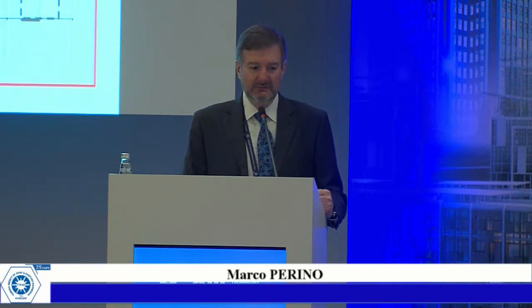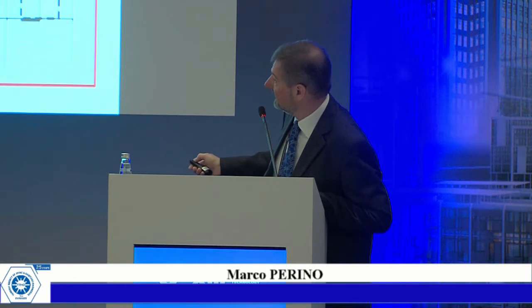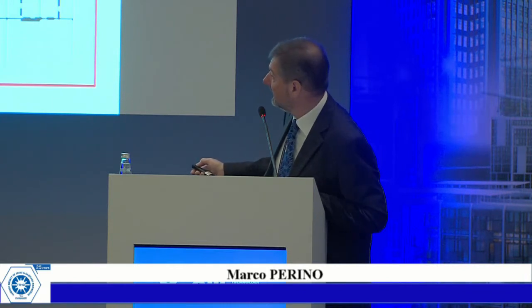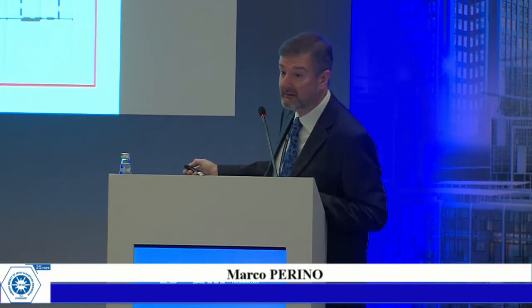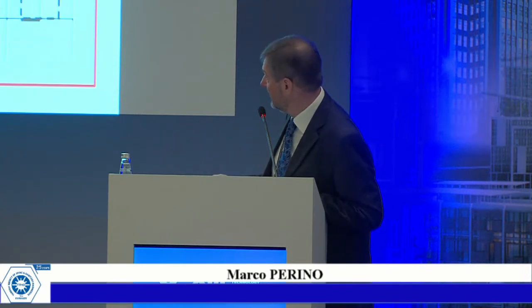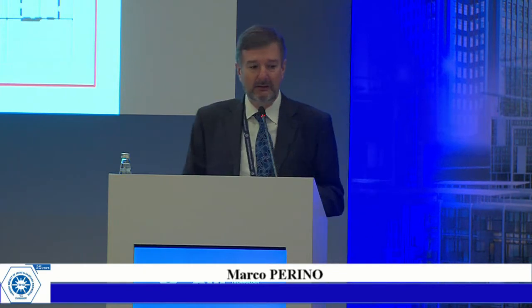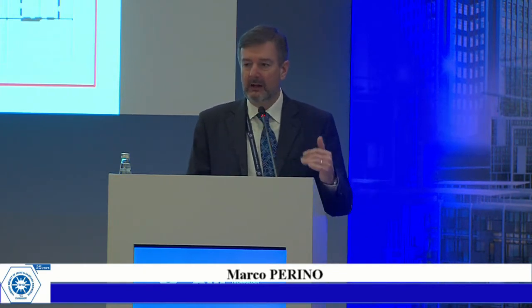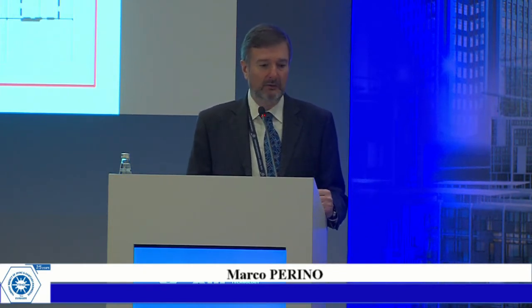Here are some measured data of energy crossing the facade. As you can see, during winter it works very, very well—most of the time you have gains instead of losses. It's still a bit to be optimized during summertime, since the entering loads are not very high, but still higher than we would like.